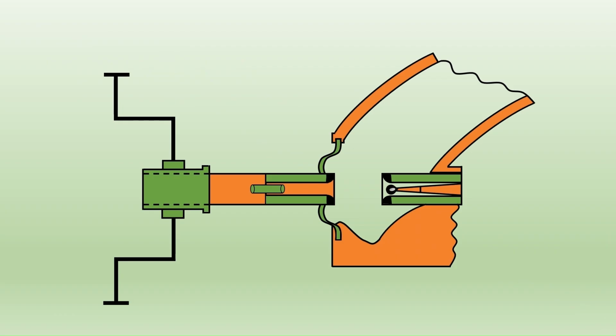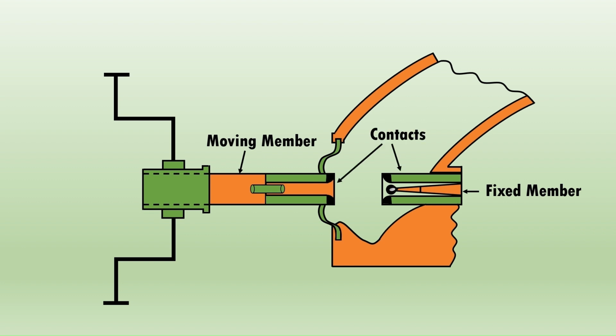The second type of SF6 circuit breaker is the non-puffer type. It has a moving member and a fixed member. The non-puffer type SF6 circuit breaker has an interrupter part. The arc quenching process is performed in this part only. It consists of two contacts, the fixed contact and the moving contact. The fixed contact has arc horns connected with it.